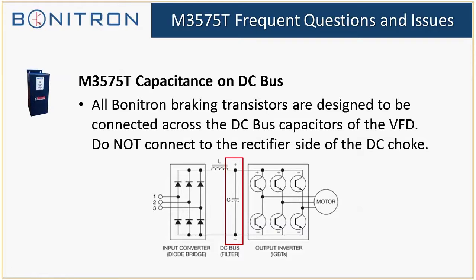Basically, this creates a problem with our choppers. Our choppers have a small snubber cap going across our transistor. The snubber cap plus the inductor creates what's called a boost circuit, and that will basically destroy the chopper. The chopper will enter a mode of rapid switching and basically harm itself. So that's why it's really important to be across the DC bus terminals if possible.